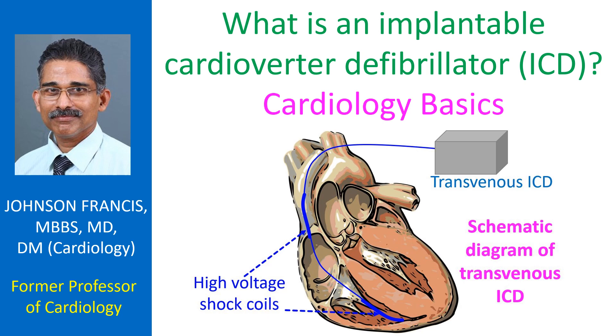The ICD senses and analyzes heart rhythm continuously. It can detect life-threatening ventricular arrhythmias and treat them electrically. If a ventricular tachycardia is detected, the ICD tries to overdrive it by fast pacing. If it does not suppress the ventricular tachycardia, the ICD delivers a shock through its high voltage coils and terminates the arrhythmia.